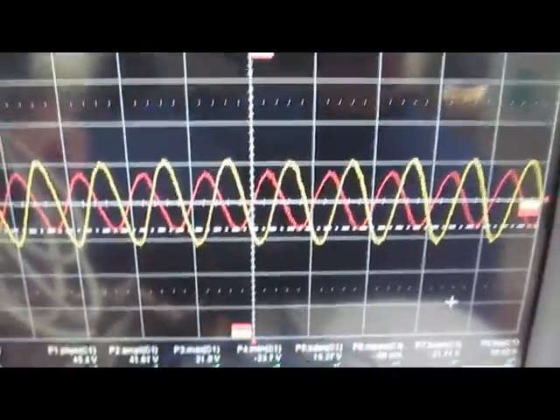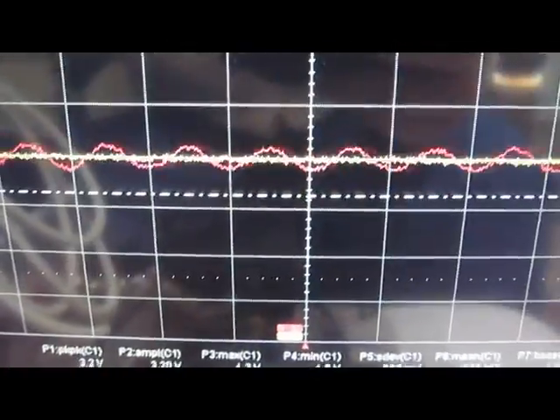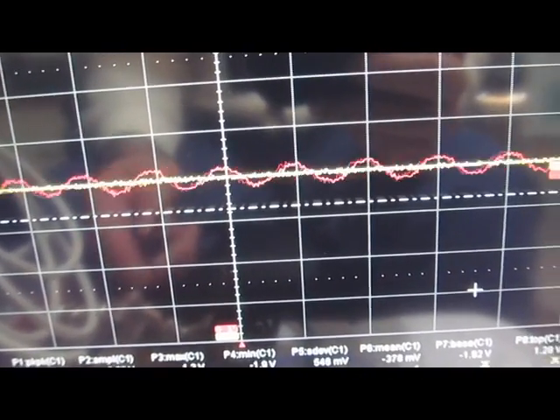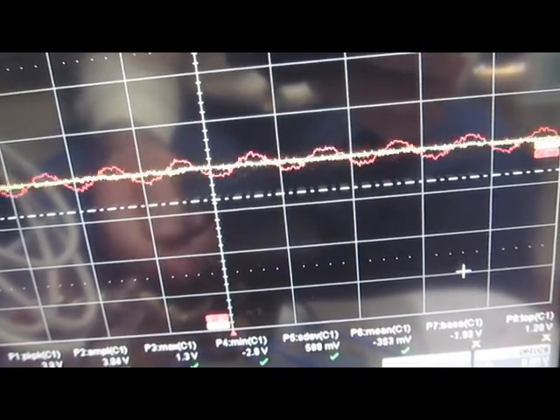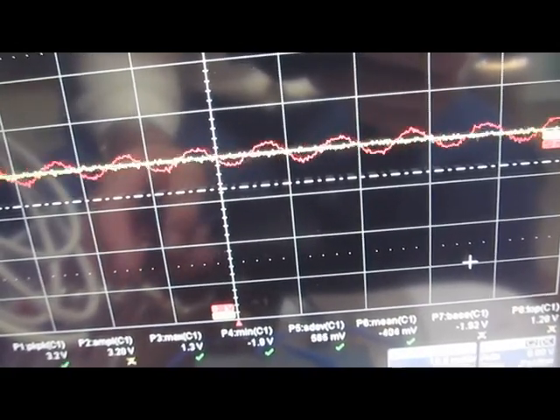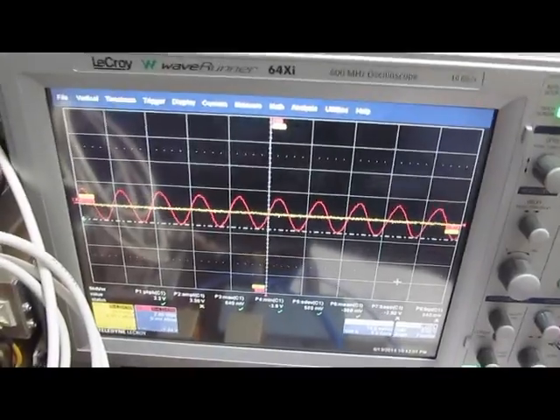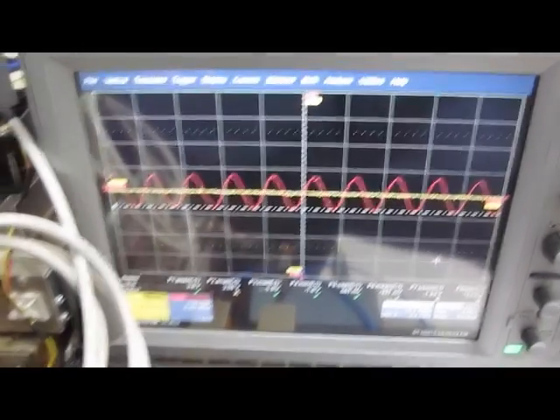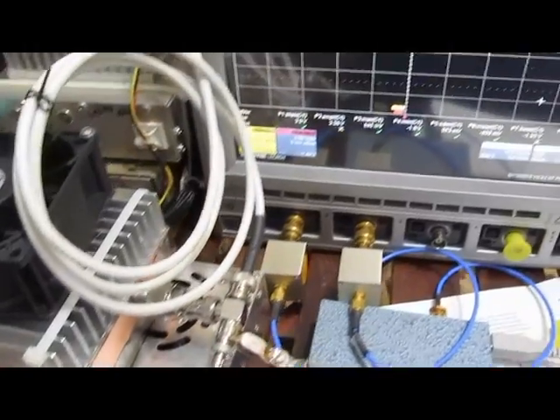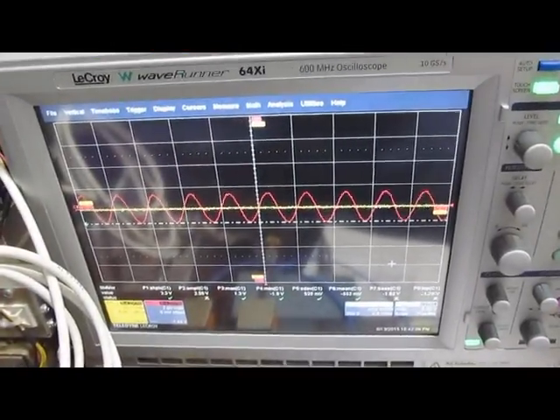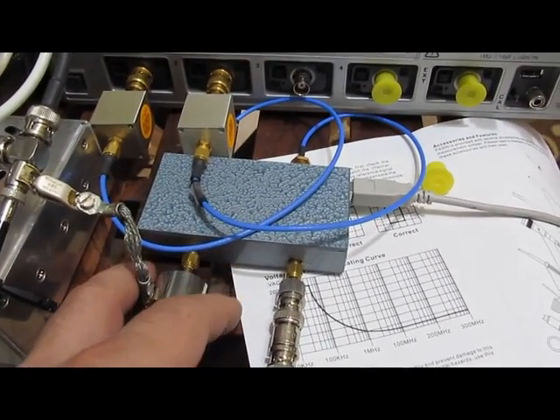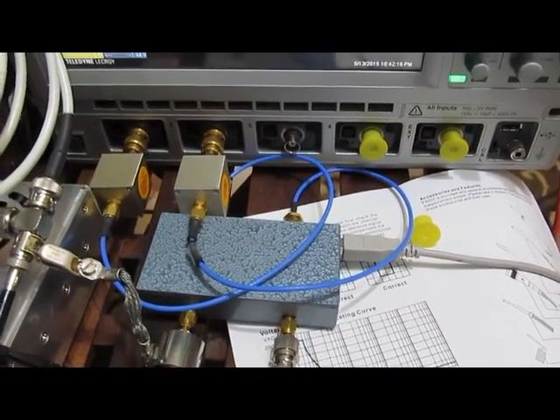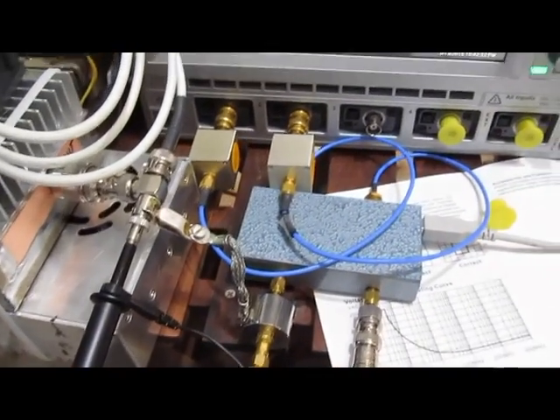Let's see how the probe just sits here and oscillates. I have to understand, I guess, what's going on with it. It really doesn't feel warm to the touch. Well, unfortunately, after several cycles, our probe is now dead completely. It appears to have opened up. I've gone on and checked all the hardware. No damage to our front end of the amplifier. Everything appears fine. It looks like just the probe itself has opened up.